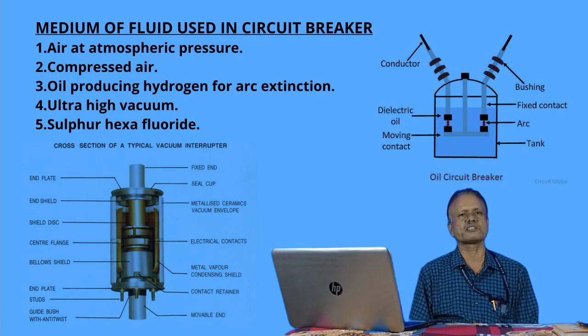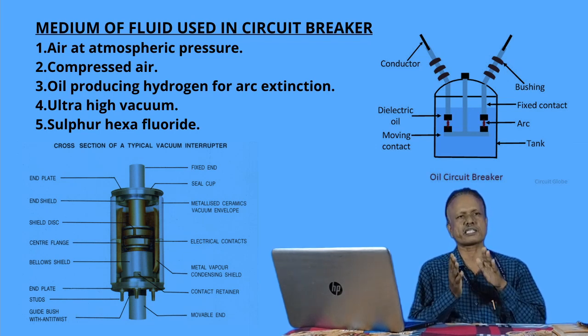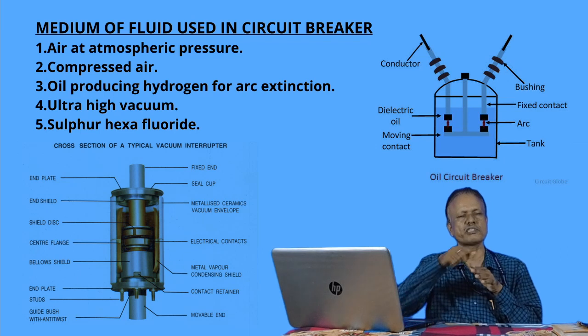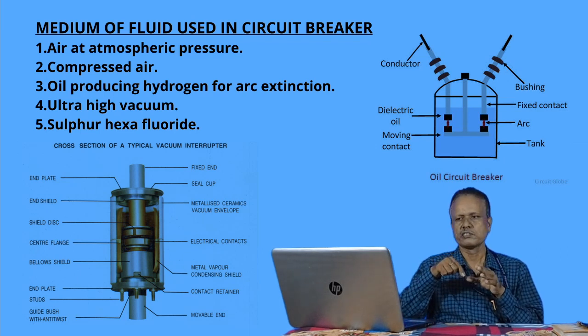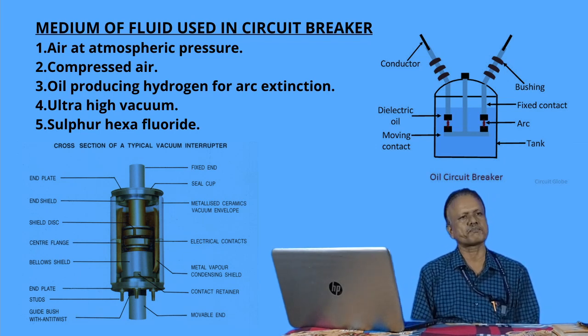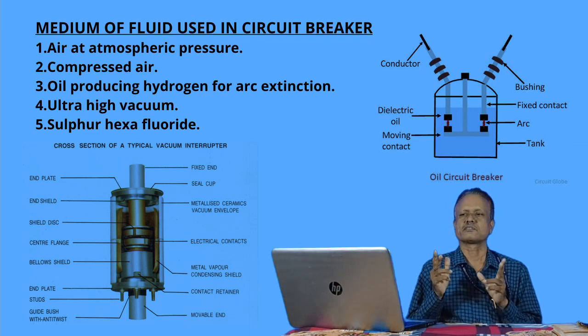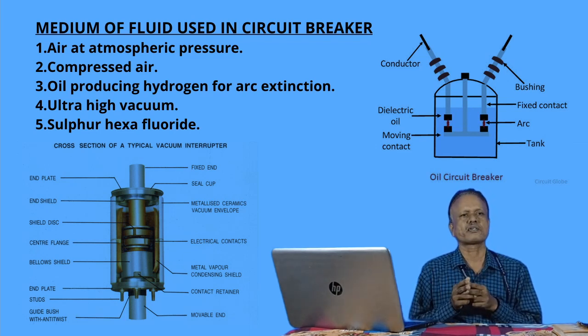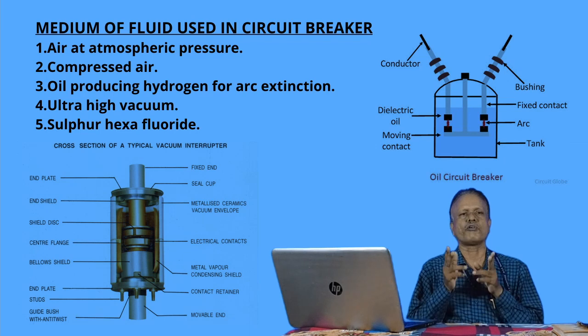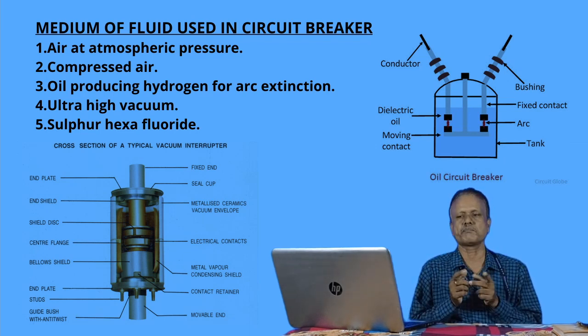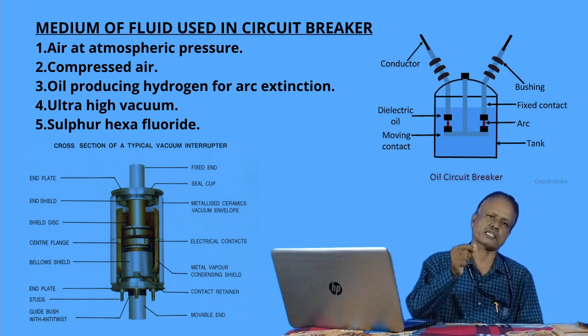Next, the medium of fluid used in the circuit breaker. Inside the circuit breaker there are two current carrying contacts, a fixed contact and a moving contact, and surrounding them there is a fluid. There are 5 types of fluids: air at atmospheric pressure, compressed air, oil producing hydrogen for arc extinction, ultra high vacuum, and sulfur hexafluoride.